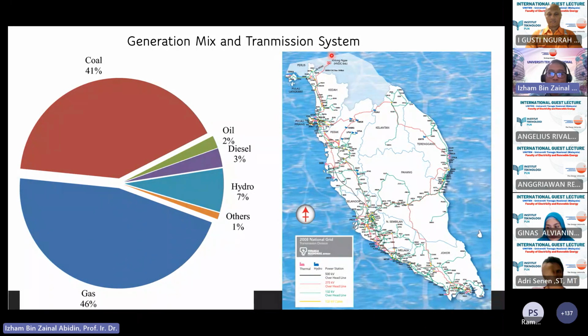However, we use HVDC just to isolate the system from different parts of other countries' networks. You must be wondering why in Thailand I have one HVDC connection, but in Singapore I don't have any HVDC connection. It's because in Singapore the power supply quality is good, so when I interconnect, I don't have issues to my system. Therefore I do not require an HVDC connection. But in Thailand at that time, TNB was worried about power quality issues coming from Thailand's side, so they installed HVDC.